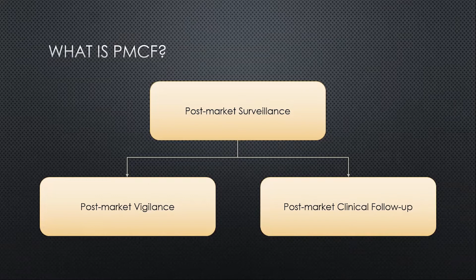It is reactive in the sense that the events have already occurred and the manufacturer monitors and performs investigational analysis to arrive at root cause for the occurrence. To sum it up, vigilance relates to a more corrective approach. PMCF, on the other hand, is a proactive process in nature. In PMCF, manufacturers plan activities that will serve to monitor the device's performance and safety post-market release. Through these activities, the manufacturers proactively undertake tasks to monitor device use in a real-world clinical setting and provide continuous assessment of the device's performance and safety profiles.